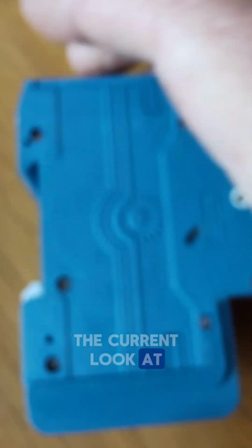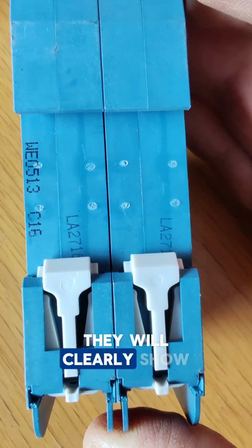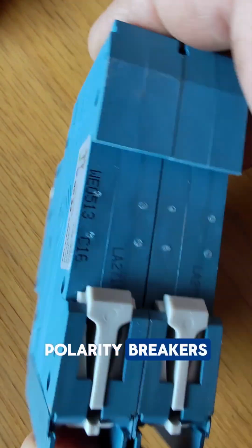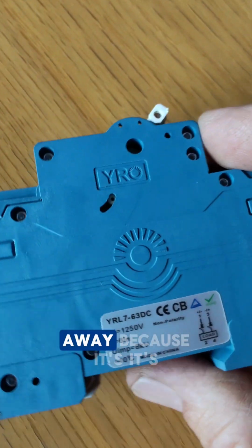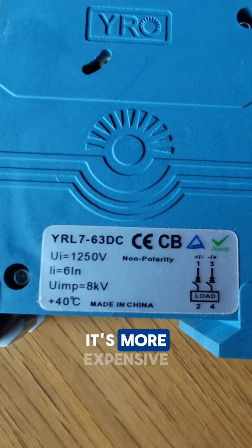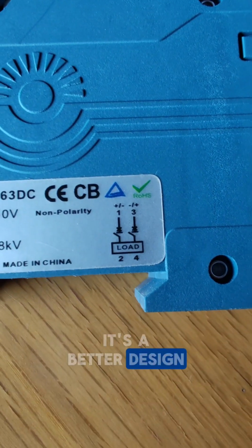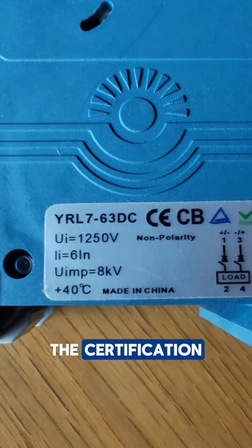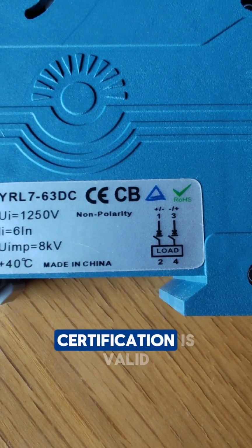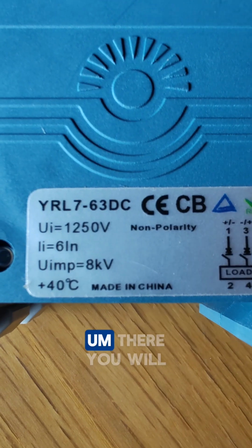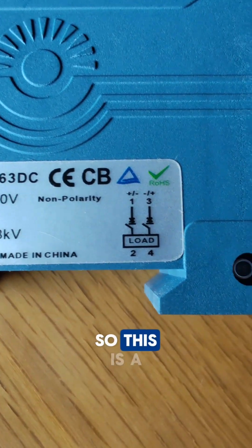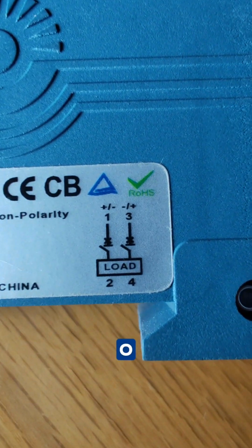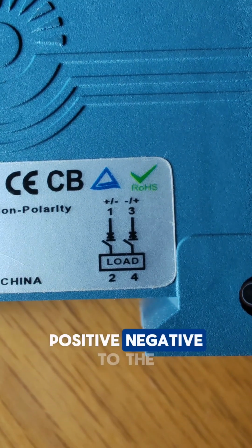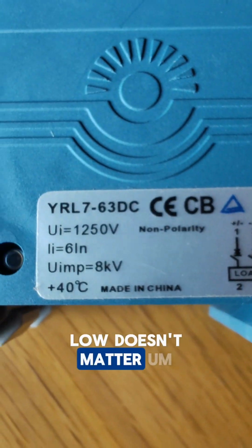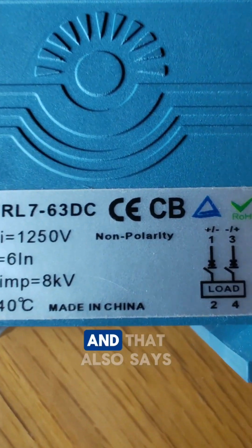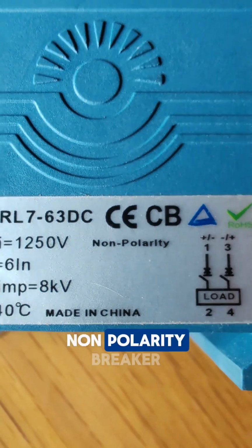Look at the breaker, they will clearly show it. When they're non-polarity breakers, they won't show it away because it's more expensive, it's a better design. There as well, look at the certification, go look at the code, see if the certification is valid. There you will get all your things. So this is a Class A from YRO. There it will also show positive, negative to the load, doesn't matter. And there it also says it's a non-polarity breaker.